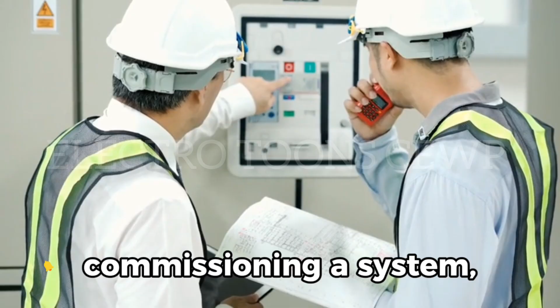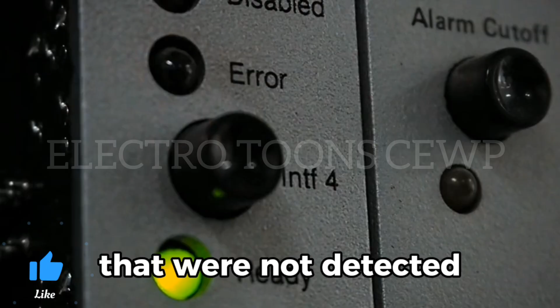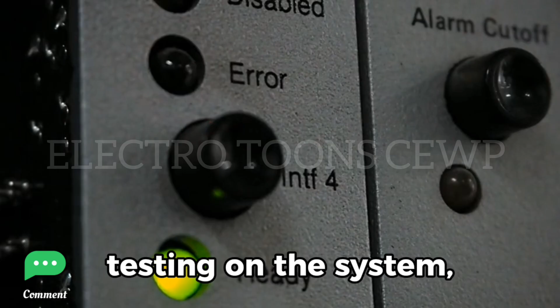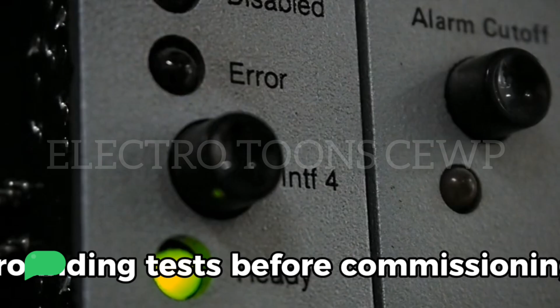Inadequate testing before commissioning. Before commissioning a system, engineers sometimes fail to test the system thoroughly. This can lead to faults that were not detected before the system goes live. How to avoid it? Perform comprehensive testing on the system, including continuity tests, insulation resistance tests, and grounding tests before commissioning.